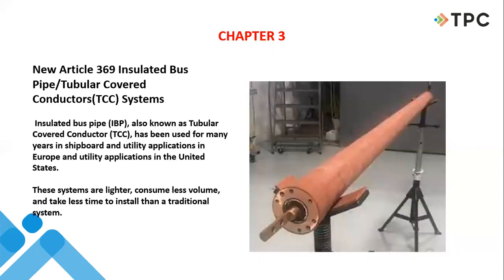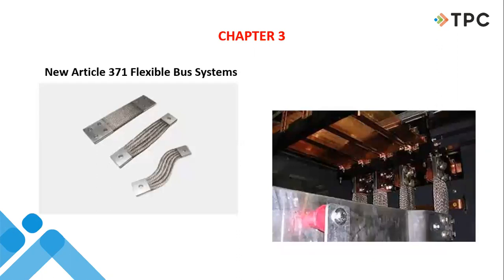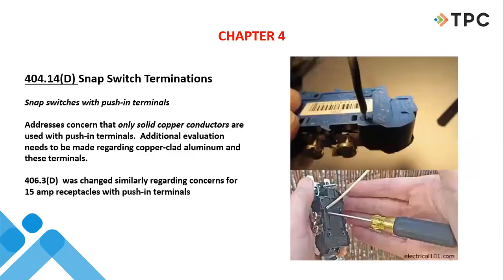A new article for insulated bus pipe, tubular covered conductors, new technology, new levels of acceptance for existing technology, code expanding, giving people other options. Flexible bus systems was given a new article, Article 371. Here's a good one. Snap switch terminations with the push-in, the so-called stab lock terminals in the back. 404.14D addresses concern that only solid copper conductors be used with push-in terminals. Additional evaluation still needs to be made regarding copper-clad aluminum in these terminals.